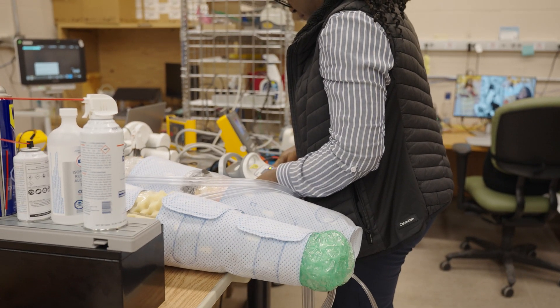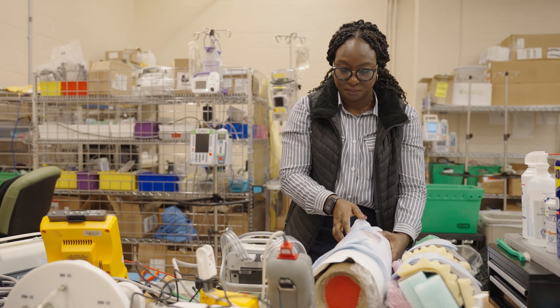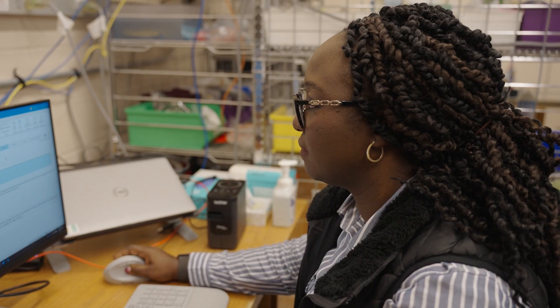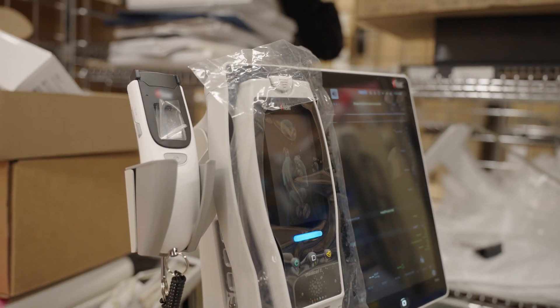We have patient simulators that output various waveforms and parameters in order to test equipment before they are put onto the patient. We also use software to troubleshoot, carry out demand maintenance, repairs and calibrations, and to pinpoint the area of fault in the equipment.